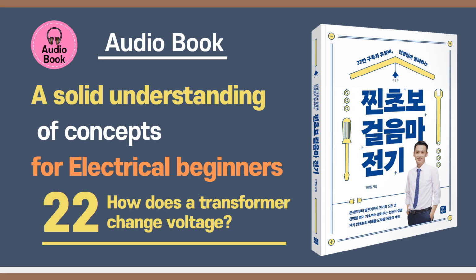But it's important to remember what they don't do, right? Absolutely crucial. Transformers are voltage and current changers, that's their job. They cannot change the frequency, 60 hertz in, 60 hertz out. And they don't make power, they don't create energy. They just convert it between voltage levels. Power in equals power out, minus those small efficiency losses we talked about, like heat from resistance and eddy currents. They obey the laws of physics, conservation of energy. So no free lunch, just repackaging the energy. A very efficient repackaging, but yes.